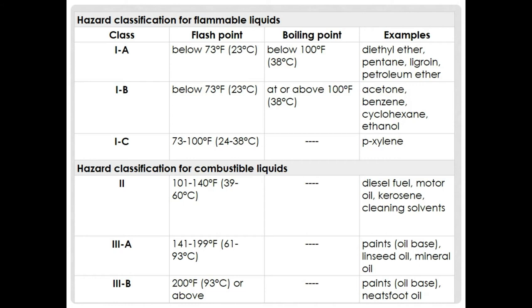For combustible liquids, the flash point is above 37.8°C. Class 2 covers 39–60°C — examples include diesel fuel, motor oil, kerosene, and cleaning solvents. Class 3A covers 61–93°C — examples include paint (oil-based) and mineral oils. Class 3B covers above 93°C — examples include certain oil-based paints and linseed oil. If combustible liquids are stored at elevated temperatures above their flash point, they can produce vapors and become flammable.